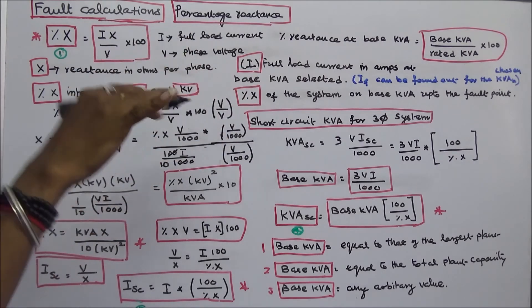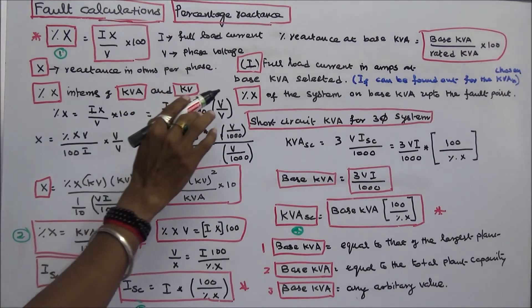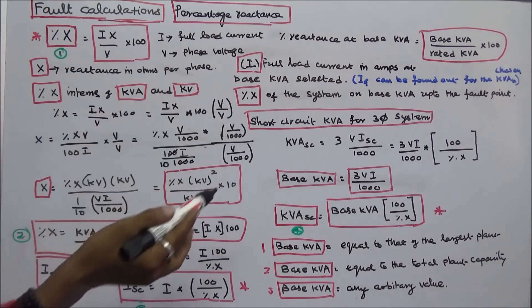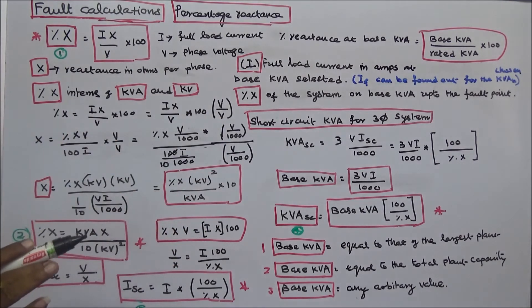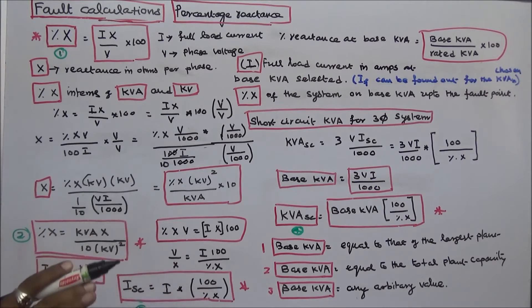Percentage reactance on base KVA equals base KVA divided by rated KVA, multiplied by 100. This gives the percentage X of the system on base KVA up to the fault point. So ISC equals I times 100 divided by percentage X.